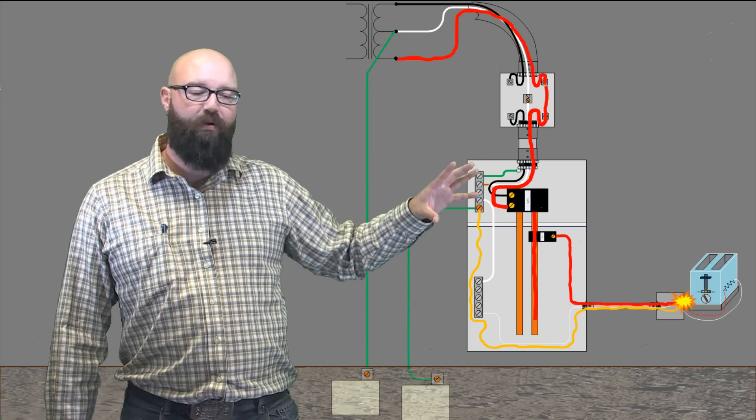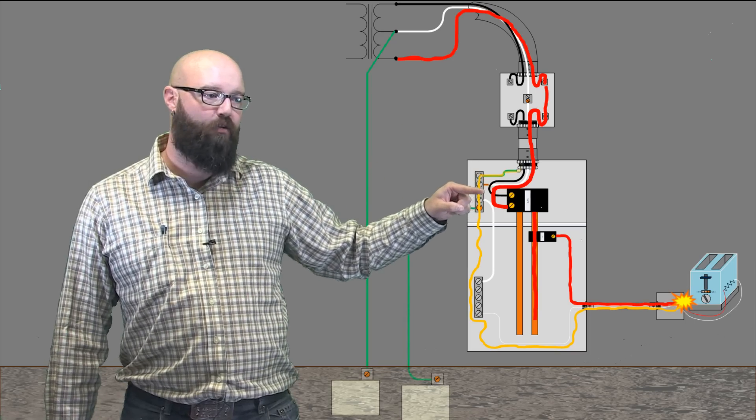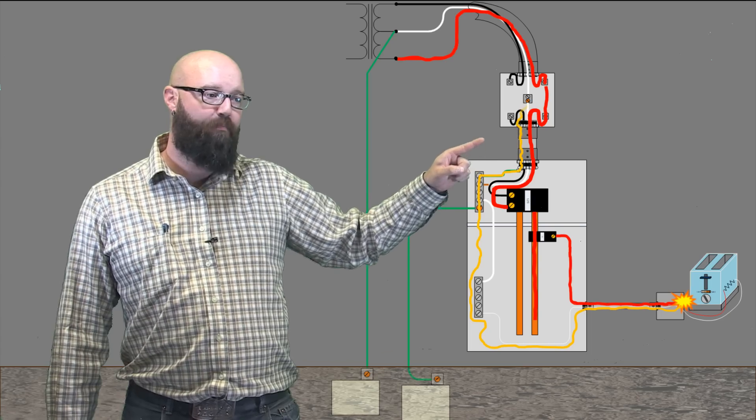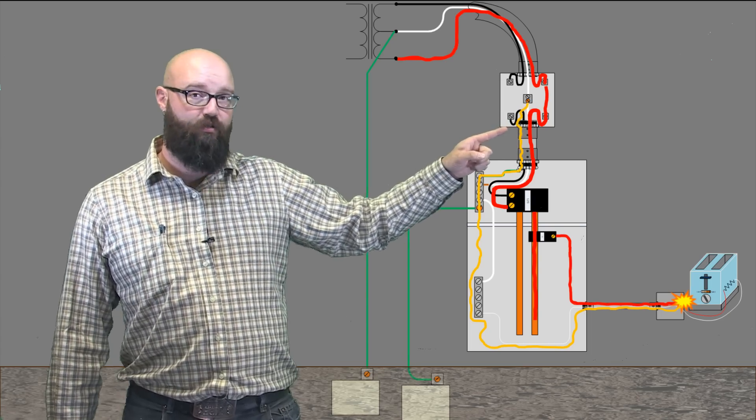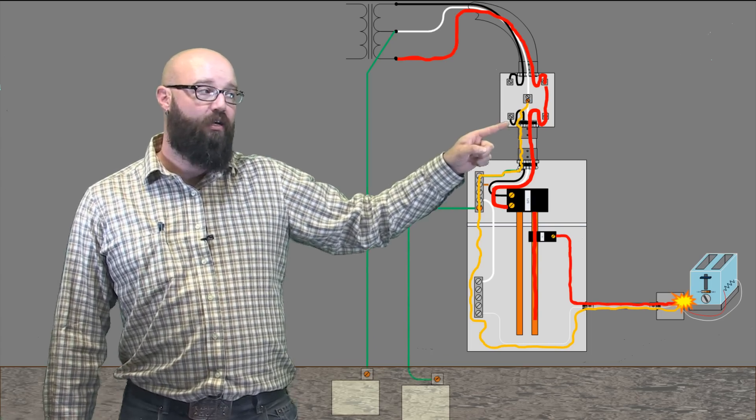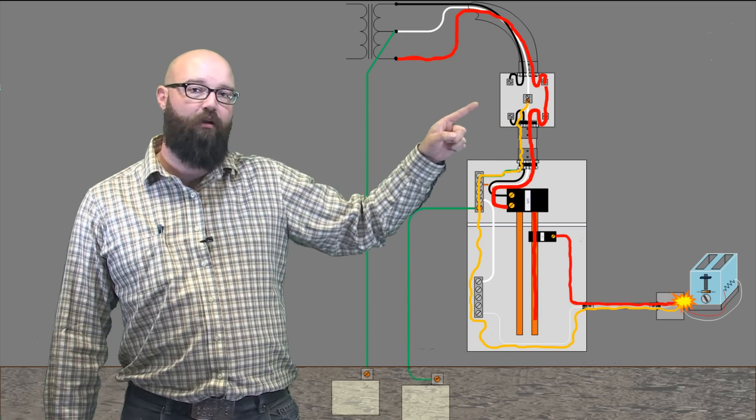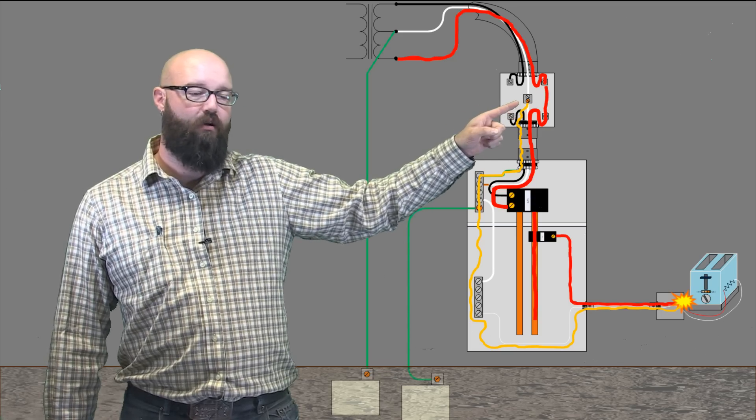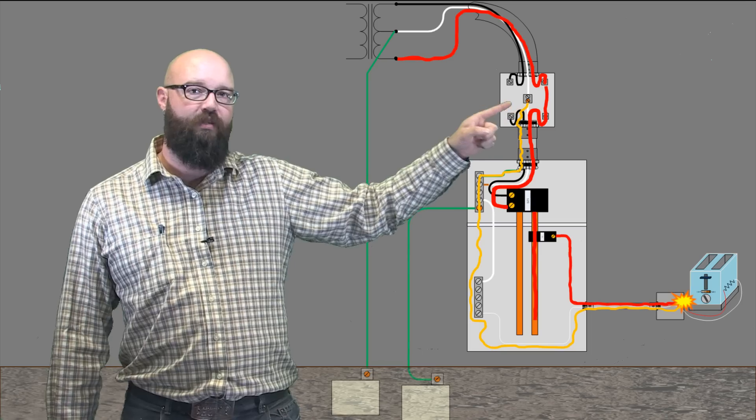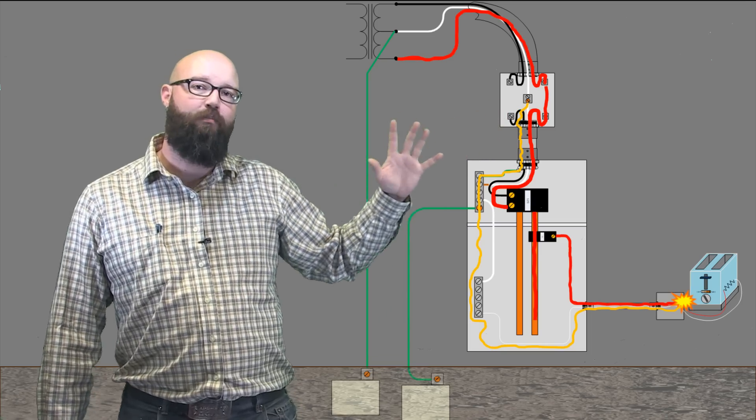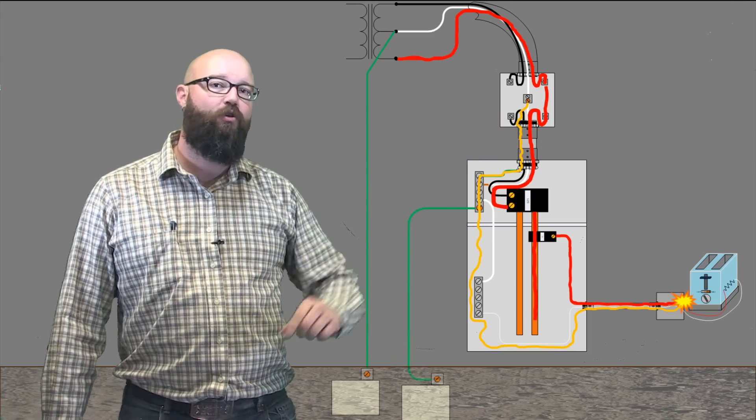Right now, if this path is intact, that fault current is going to make its way up the grounding bar, up that conduit, that service raceway, which is metal, which is attached to this metal meter base, which if you notice right here, we have another brass screw. And the intent of that brass screw is to bond our meter base to our neutral conductor.